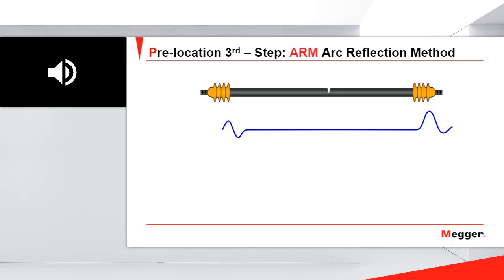Okay, we don't have anything at the fault because, as I said in the previous slide, this low voltage pulse does not have enough energy to flash over the fault. So the pulse continues, nothing, a flat line, and we have the end of the cable over here.